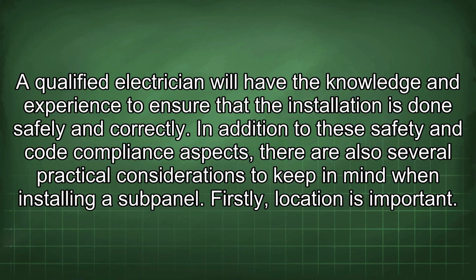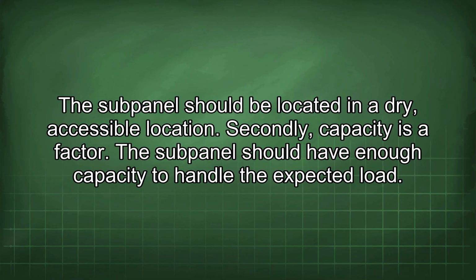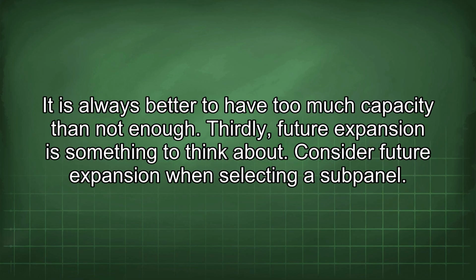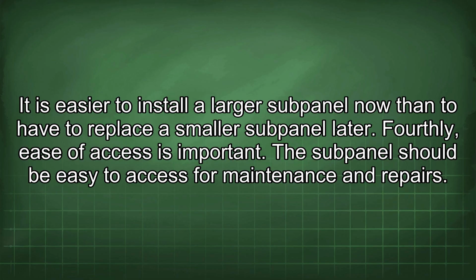In addition to these safety and code compliance aspects, there are also several practical considerations to keep in mind when installing a subpanel. Firstly, location is important. The subpanel should be located in a dry, accessible location. Secondly, capacity is a factor. The subpanel should have enough capacity to handle the expected load. It is always better to have too much capacity than not enough. Thirdly, future expansion is something to think about. Consider future expansion when selecting a subpanel. It is easier to install a larger subpanel now than to have to replace a smaller subpanel later.